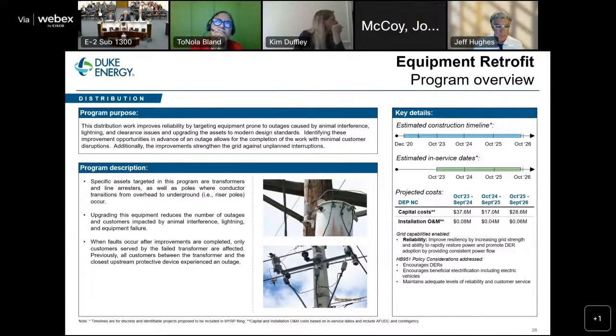First, we install local fuses. That way, if there's a problem at that device, only the customers served by that particular asset experience an outage. Without local fuses, the outage extends further out to the next protected device, and customers who don't need to be out based on that failure experience an outage anyway.